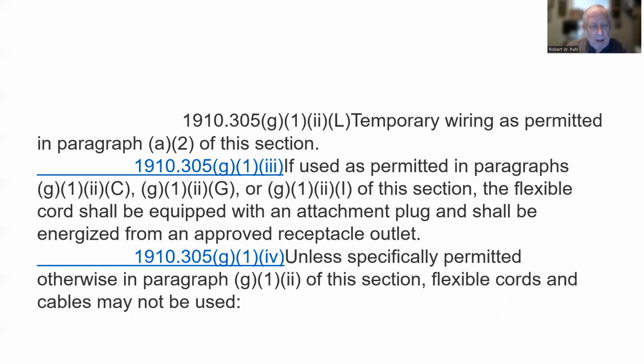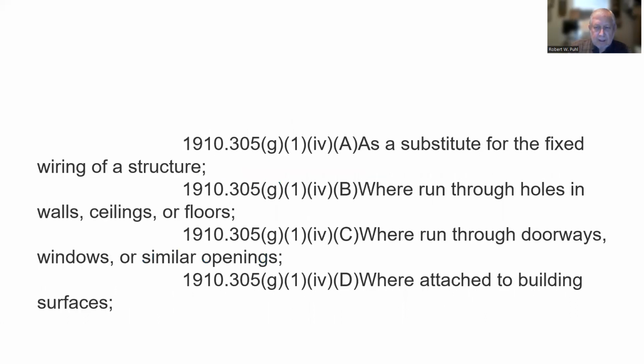If used as permitted in paragraphs G, C, and I, the flexible cord shall be equipped with an attachment plug and shall be energized from an approved receptacle outlet. Unless specifically permitted otherwise in paragraph G1II, the section flexible cords and cables may not be used as a substitute for the fixed wiring of a structure. That's something you're going to look for. Flexible cords cannot be used for fixed wiring. Now you see a piece of equipment that's got a flexible cord running onto it, and instead of running a conduit to it, that's a no-no. You've got to have fixed. If it's a fixed piece of equipment, it should be hardwired in.